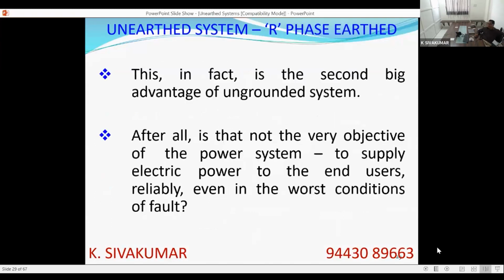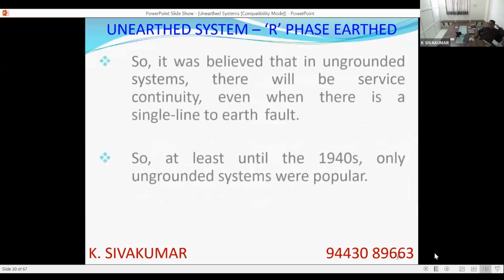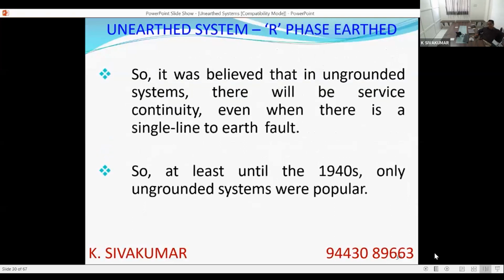So this was perceived to be the second advantage of the ungrounded system. I say this was perceived. Power system engineers will agree with me, the very objective of the power system is to supply electric power to the end user, even in the worst conditions. So even in the worst condition of a single phase ground fault, there is no interruption. Power supply will continue to go to the customer in an ungrounded system. So not surprisingly, it was believed that in an ungrounded system there will be service continuity even when there is a single line to earth fault.